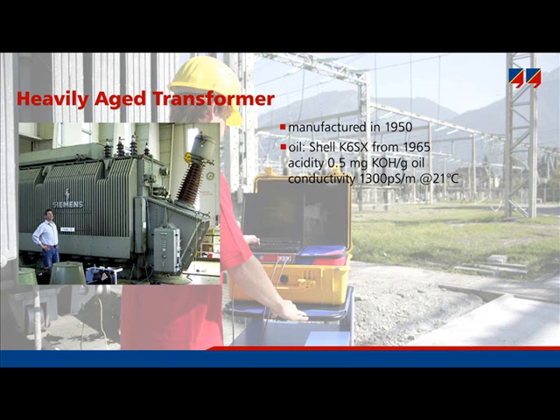Aging byproducts such as acids increase the losses and therefore the conductivity of the oil. However, on this transformer, the degree of polymerization was about 600 to 700, which means that mechanically the insulation was still in moderately good condition.